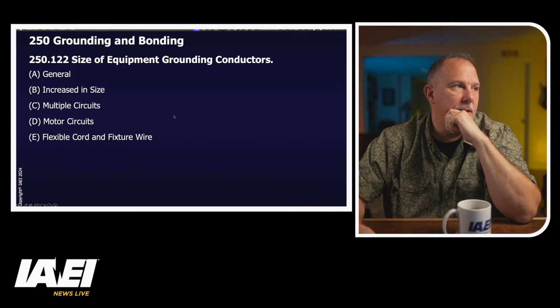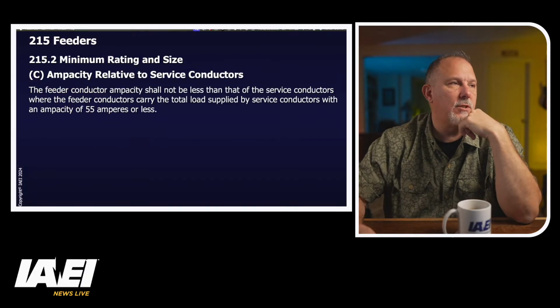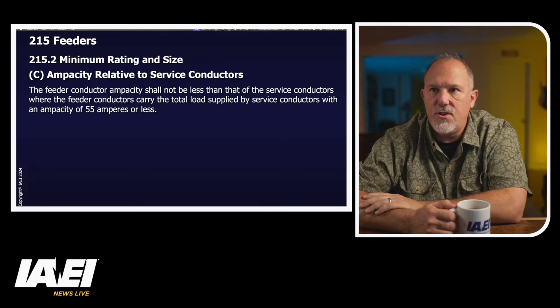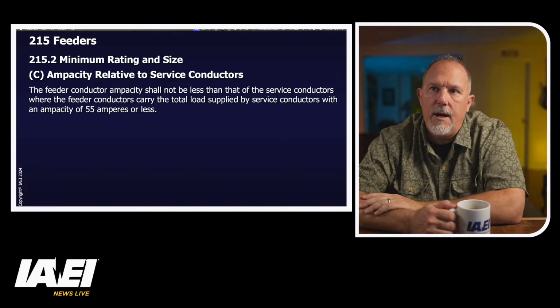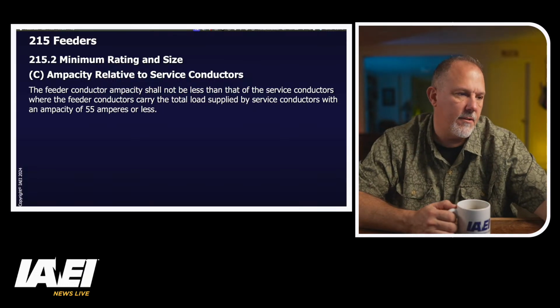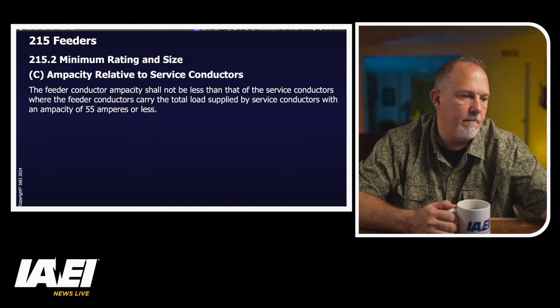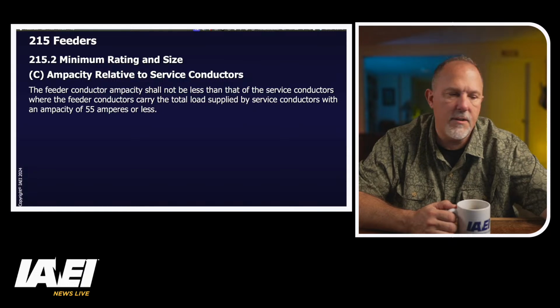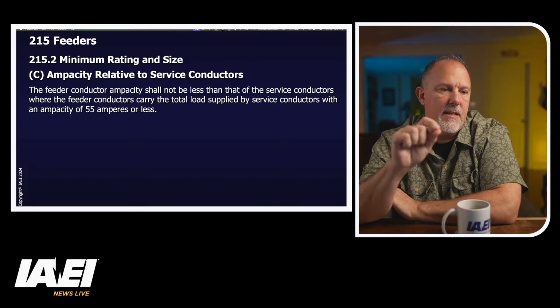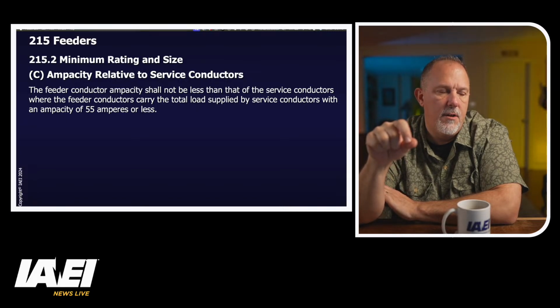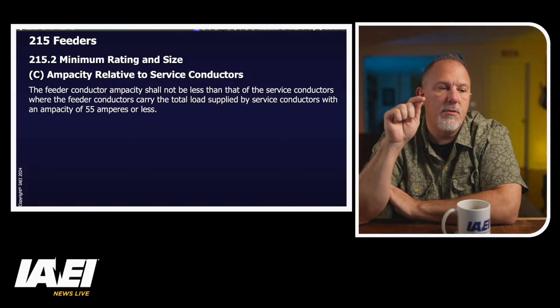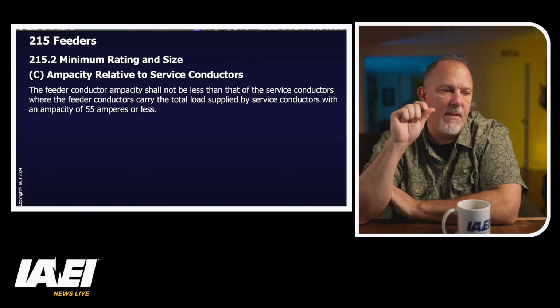So let's take a look at, okay, those are all of the conditions in 250.122. So let's take a look at 215.2. Minimum rating and size. This is the ampacity relative to service conductors. This is 215.2(C). So what this says, the feeder conductor ampacity shall not be less than that of the service conductors, where the feeder conductors carry the total load supplied by service conductors with an ampacity of 55 amps or less.